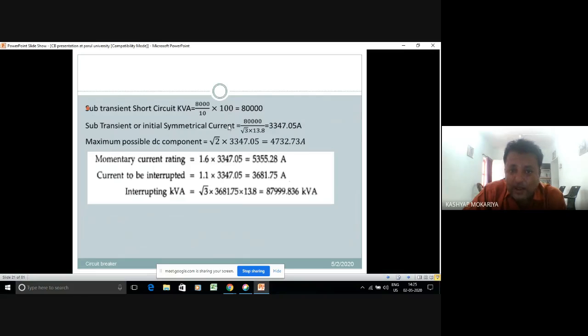This is the kVA capacity. So I get the symmetrical current is equal to 3347. And if somebody asked what the DC component from this current was, I got the maximum possible DC component is equal to root 3 times root 2 times the peak value from this. So I will get 4732.73 ampere.